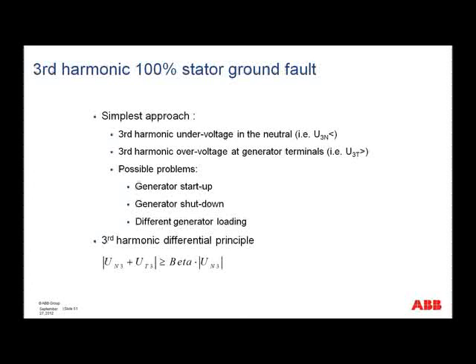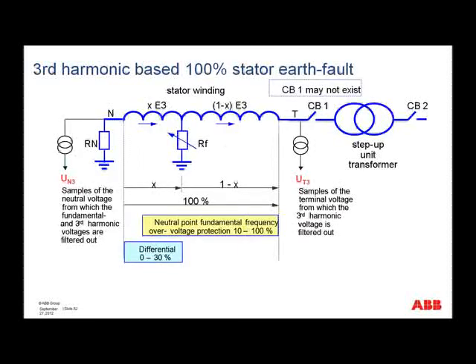So the best method to use then, if you're using the third harmonic, is to use the third harmonic differential principle, in which you calculate an operate quantity and a restrain quantity. Now, I don't want to go into that in too much detail right now, but what's important, if you just have a look at this picture, you see then the whole stator winding here. Okay, now remember what we said previously, that using the fundamental frequency, either voltage-based or current-based detection of stator ground faults, it was not possible to see the last 5 or 10%, depending on the threshold of the pickup, right at the star point. Now, this third harmonic-based differential function, that is where it is operating, and it covers really only roughly the bottom, somewhere around 20–30% of the winding.